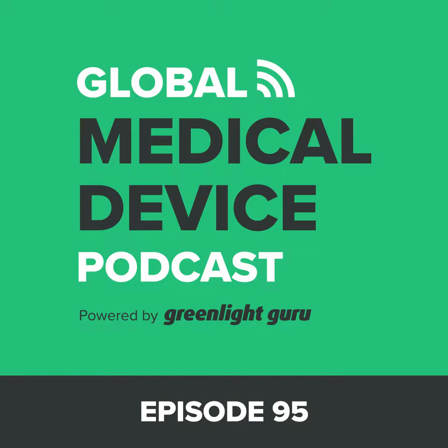So if it's got non-significant risk, let's just say you have a device that was labeled, you went through and even did a clinical trial, and during that clinical trial you went through IRB protocols and it was listed as a non-significant risk device, you still need to have something in your file that you've addressed it. I would recommend that you have a pre-sub meeting with FDA if you're seeking FDA clearance that assures that you are addressing all of their questions in your file in case you're audited.